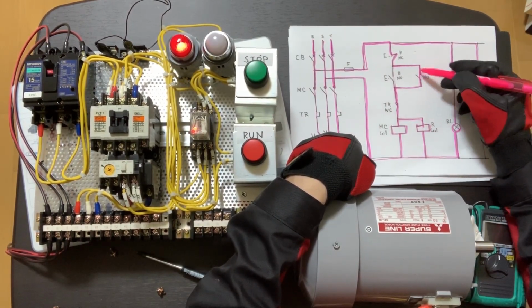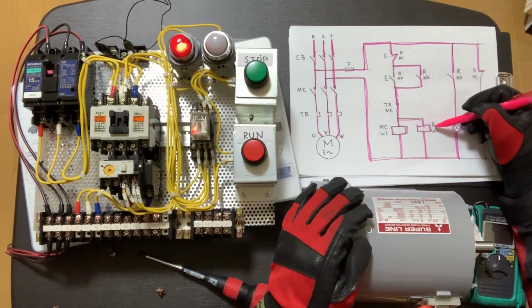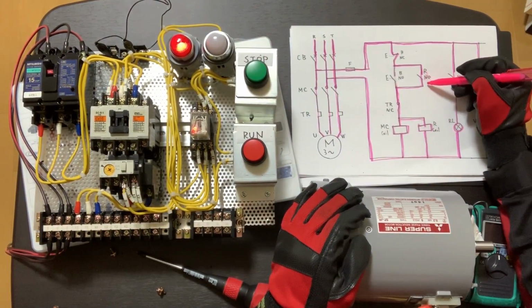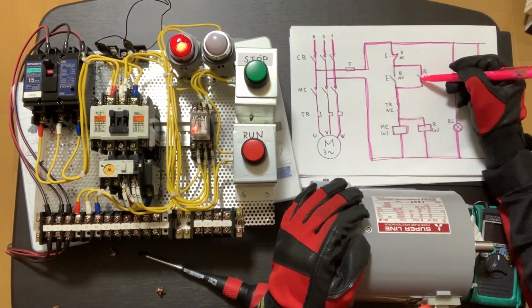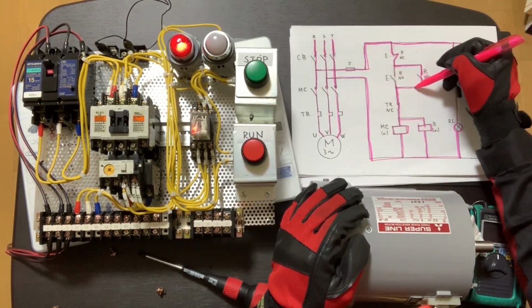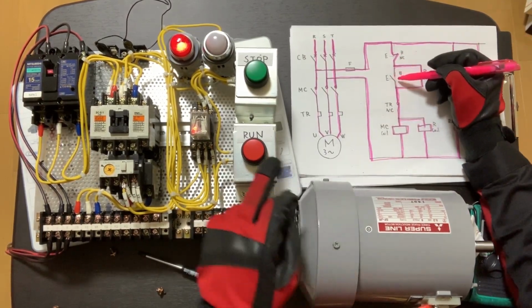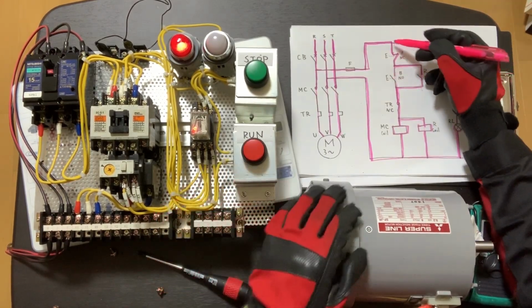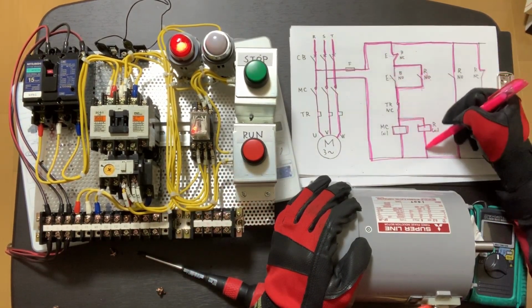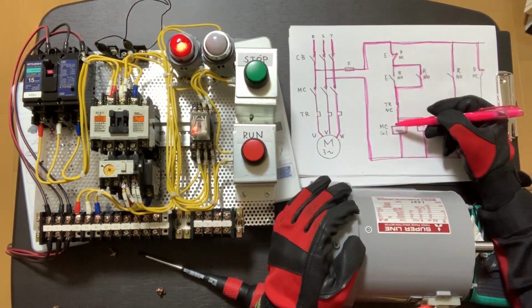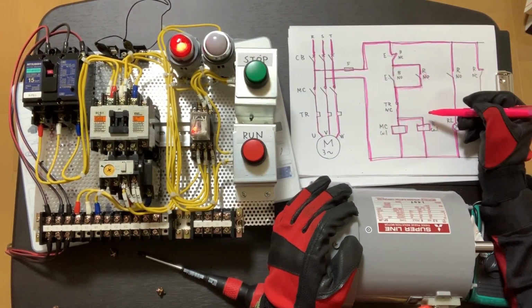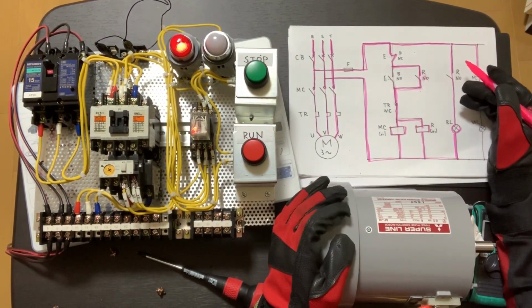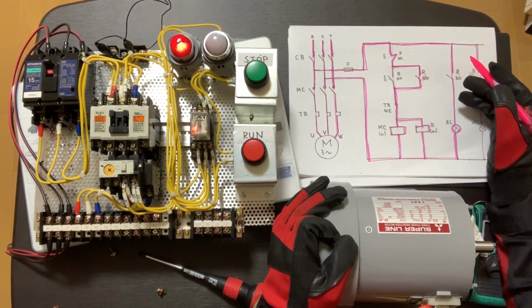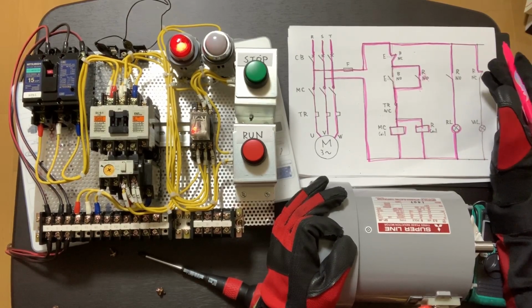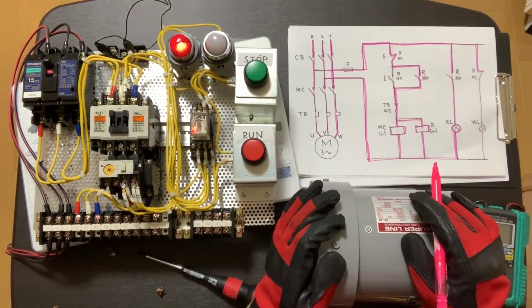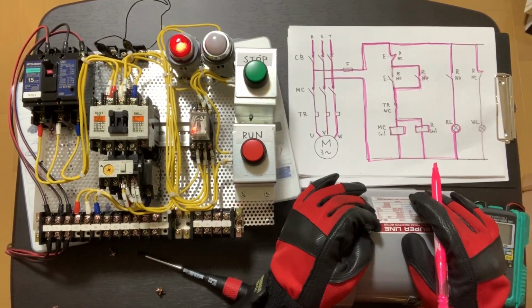I mean, this connection is the relay's normally open contact, but it's energized and turned to closed, so even if this push button turns to open, this route still keeps the magnetic coil and relay energized. Interesting. It's called a self-holding circuit. It's very important in control circuit analysis.